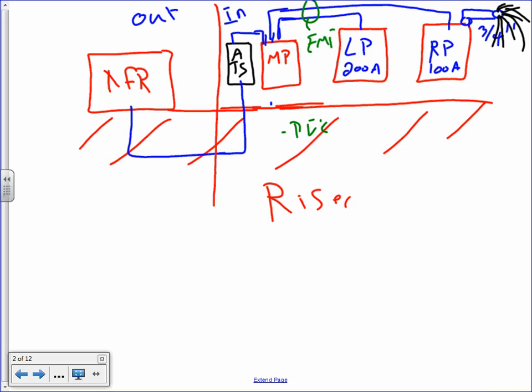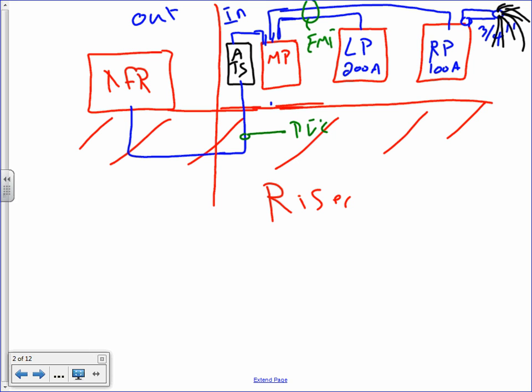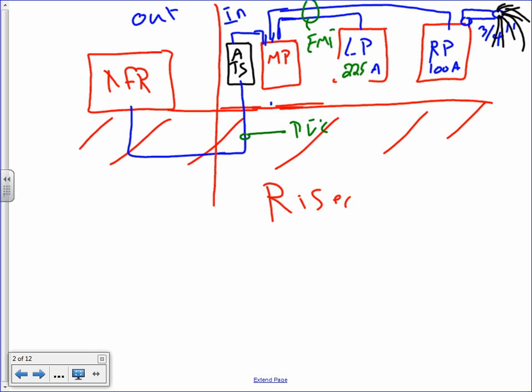This one is going to be PVC, definitely. Everything else is EMT. Can you guys see that? I have an auto transfer switch feeding the main panel. The 2 panels are feeding 200 amp. And my lighting panel, Jeff, we changed it into what? You guys remember? 225 amp. Please change that one to a 225 amp panel. And so when you build your riser tomorrow, and this has to be 500 amp, 500 amp. When you guys are sizing your system, your riser is going to look exactly like this tomorrow in Revit.